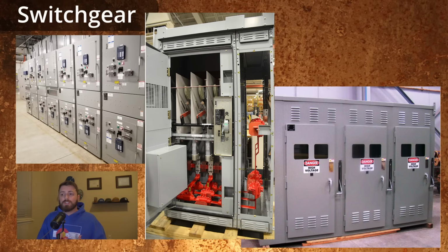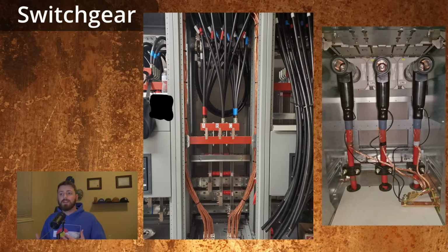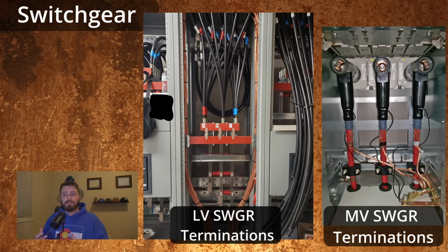Since the size, voltage, and construction of these vary so much, it's kind of hard to make firm rules on what switchgear actually is. But the key thing is that every breaker or switch has its own compartment, and the primary current-carrying connections are at the rear of the breakers, which attach to the bus deep into the back of the enclosure. For switchgear, there will almost always be rear access behind the switchgear so that feeder cables can be pulled in and landed on the termination points inside the enclosure.